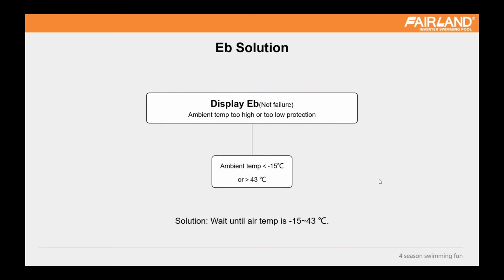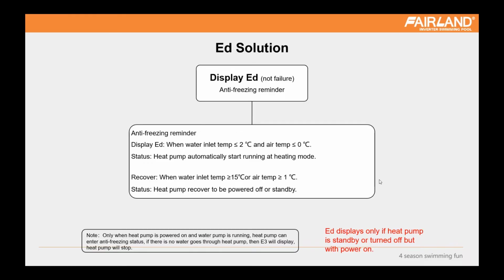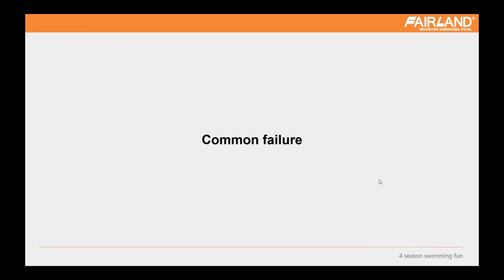Eb is for units where the ambient temperature is too high or too low, out of the normal range. I don't think it will happen in your country, unless it is more than 43. So just check the local weather. ED is again an anti-freezing reminder. It is a setting for very cold areas, like the Nordic countries. Those are the failures with codes.